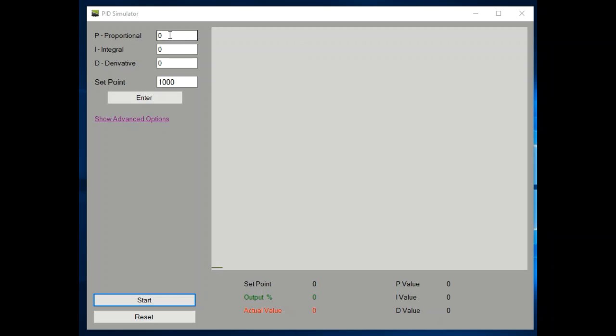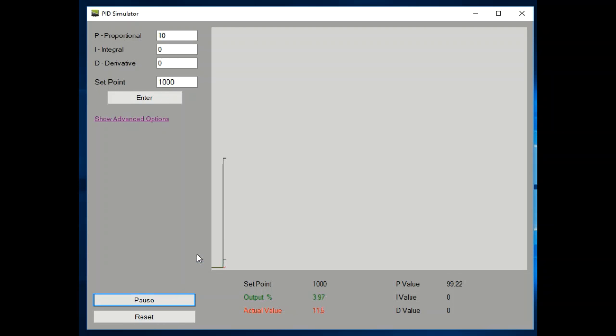Always start with the proportional — set the I and D to 0 and start with your proportional. We're going to start small because I'm not really sure how this controller is going to react yet. Starting with the value of 10, let's see what happens. A small increase in the proportional, the output is low, and the actual value is nowhere near the set point.